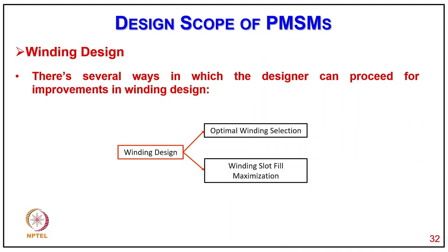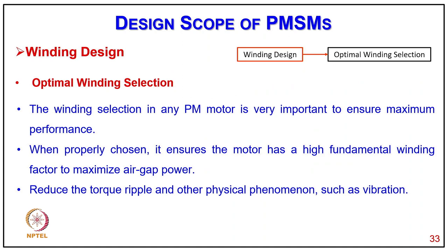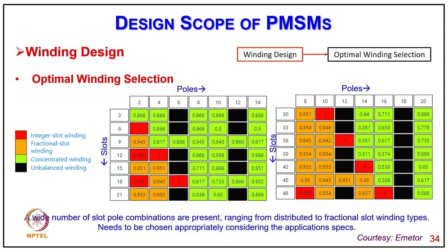Coming to winding design, there are several ways to improve winding design: optimum winding selection and winding slot fill maximization. Winding selection in any PM motor is very important to ensure maximum performance. When properly chosen, it ensures the motor has the higher fundamental winding factor to maximize the air gap power and reduce torque ripple and other physical phenomena such as vibration. Diagrams show optimum winding selection for different poles with winding factors: integral slot winding in red, fractional-slot winding in orange, concentrated winding in green, and unbalanced winding in black.